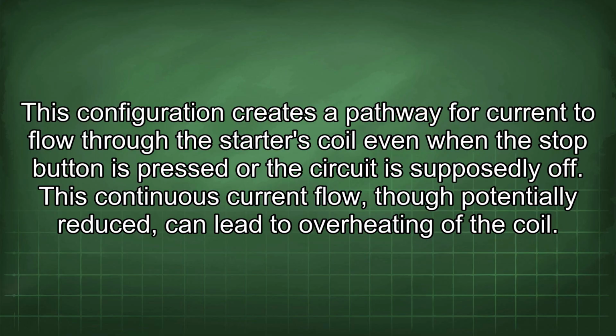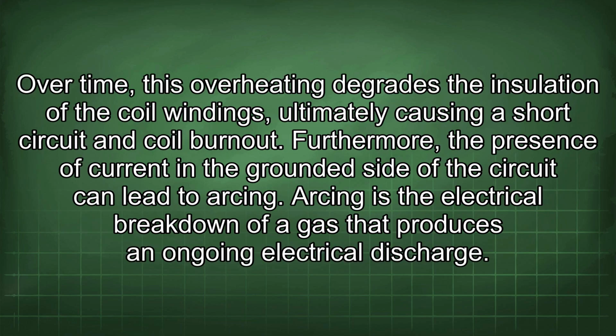This continuous current flow, though potentially reduced, can lead to overheating of the coil. Over time, this overheating degrades the insulation of the coil windings, ultimately causing a short circuit and coil burnout.